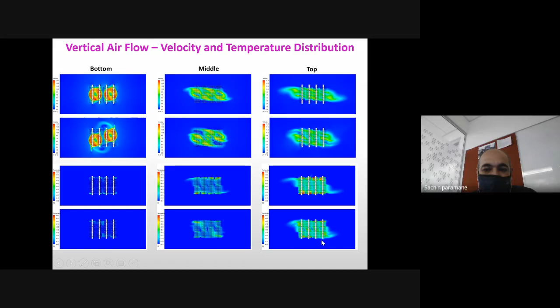Similarly, at bottom you can see the temperature distribution. You can see here the inline configuration temperature distribution is quite on the higher side, whereas it is lower when the fans are offset. Again, here a similar comparison is made for both the configurations, inline and offset. And you can see that there is again a sideways escape of the air when the fan is blowing the air in the vertical direction. And here also we are getting around 10% improvement using different fans and by changing the offset. So this concludes that by just offsetting the fans in a vertical airflow, we are getting 10 to 11% improvement in the heat dissipation.